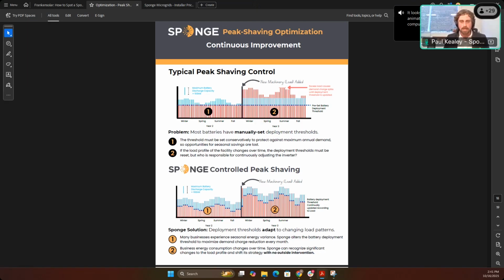Additionally, let's say you install a peak shaving strategy, and three years out, the factory you installed it on is doing quite well, so they buy new machinery, and that fundamentally alters the peak profile, the load profile of that facility. So now, three months after that purchase, you've got an angry client calling, asking why their demand charge bill is so high, and again you're driving out to site to try and recommission this system to meet the new load profile.